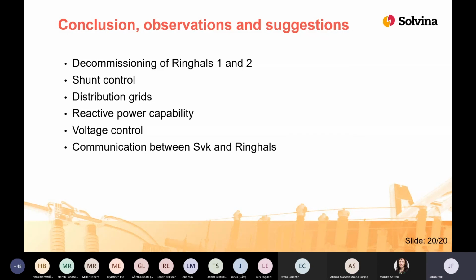Regarding reactive power capability, as I said, the decommissioning will be followed by a reduction in capacity in the region. The STATCOM and the Southwest link will add capacity, but maybe it could be of interest to study this in greater detail, since we could see in the historical grid data that the reactive power capability of Ringhals is used to a fairly high degree. On the topic of voltage control, apart from the capacity, the voltage control and the voltage stability in the area may need to be studied more in detail as well.